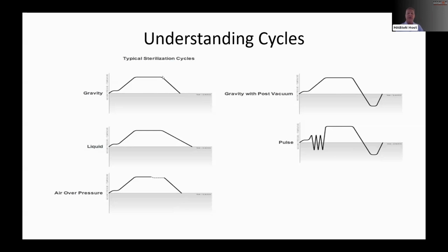Now, if you had any liquids in here on a gravity cycle, and gravity is pretty much how it works: the valve opens, the steam comes in, you run your sterilization, it opens up, and then it drops off. When it drops off, if you have any liquids in there and you open that valve, the water is not boiling yet, but the minute you release that pressure, it's an instant volcano. At the snap of your finger, it will absolutely erupt. Anybody that's tried to do liquids in their autoclave on this cycle ends up with almost no liquid in their beaker or flask.